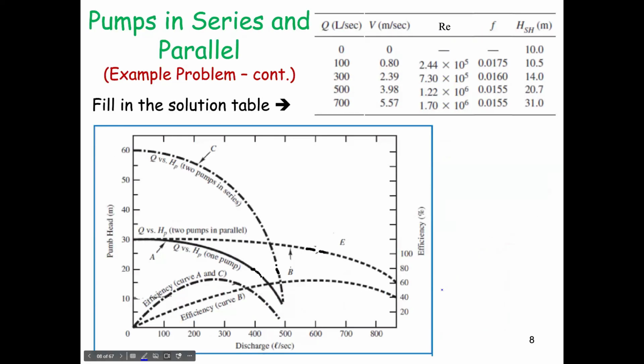Here is the one that the manufacturer gives to you. Look here, you have data for 2 pumps in parallel, in series, and 1 pump. Now, I want you to draw your graph based on Q and HS. This is your characteristic curve. Find this line for me and the matching point with this guy, and this guy gives you your Q for each of them.